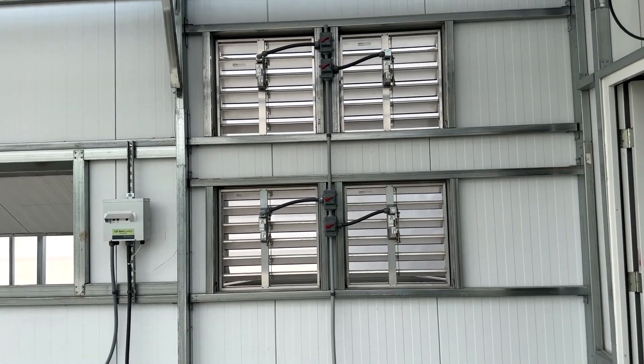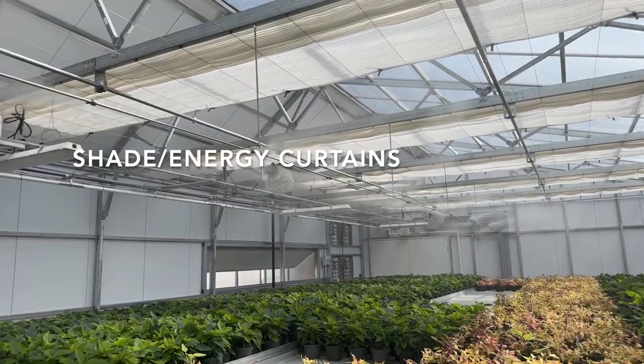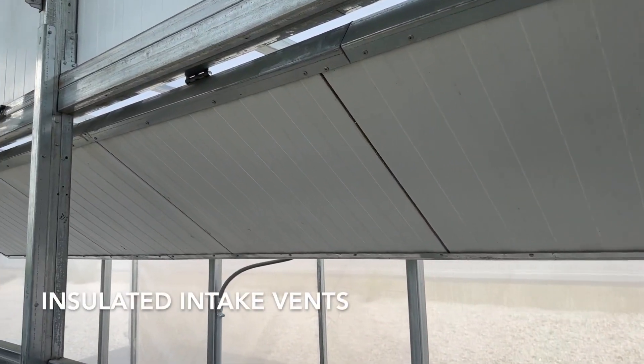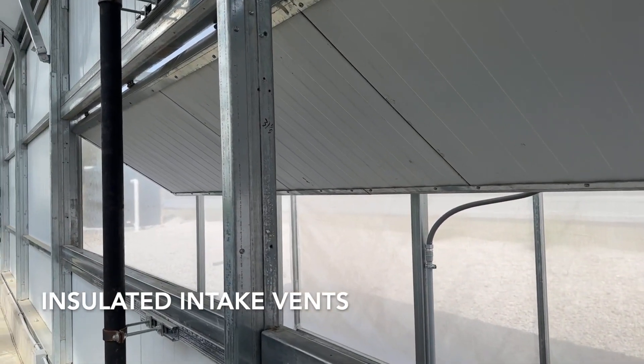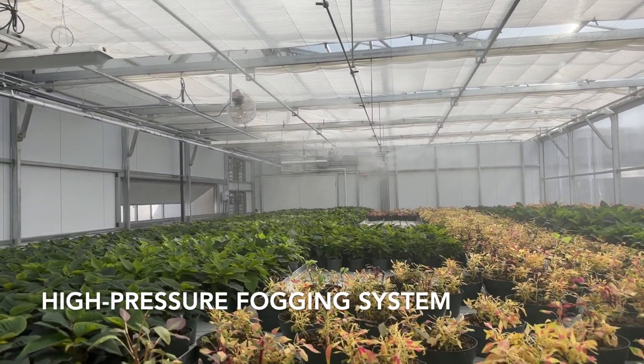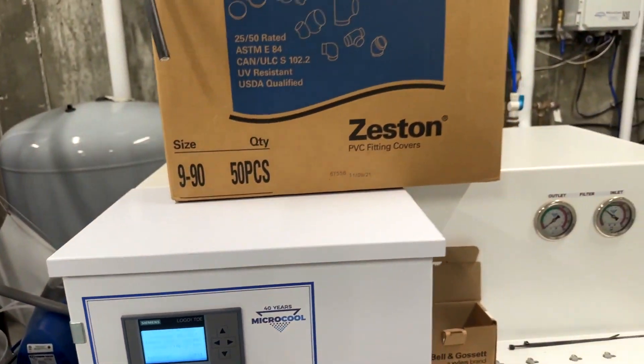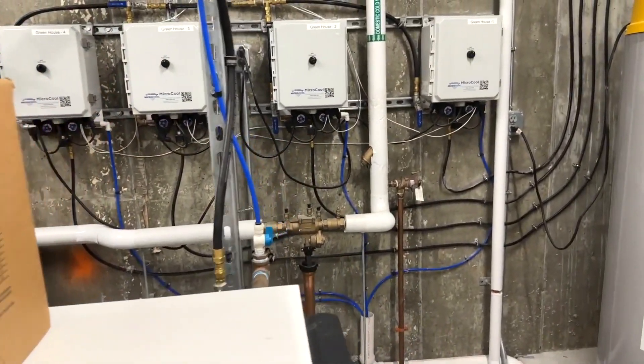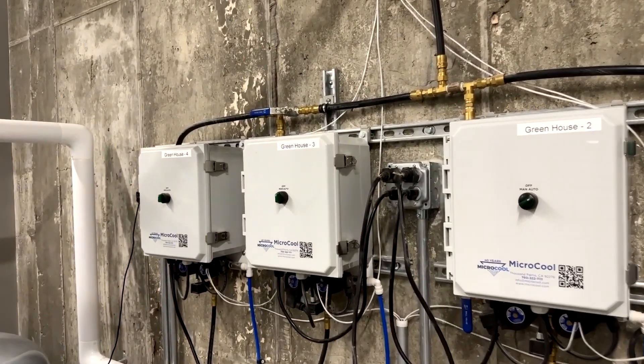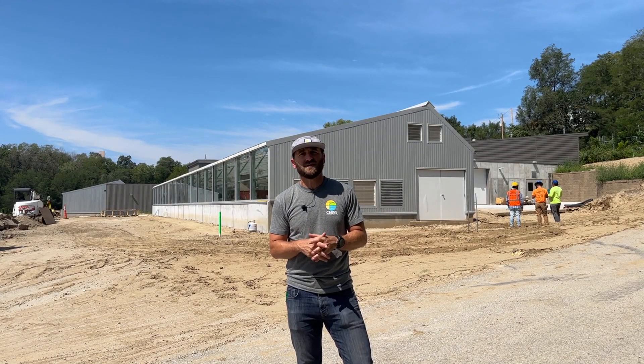It's beautiful and highly functional. The growers are excited, we're excited, and we could focus on just the greenhouses and the systems. These are vented greenhouses — all four of them. They all have shade curtains, energy curtains, exhaust fans, insulated intake louvers, and a high-pressure fogging system throughout. In a facility like this with four greenhouses, we can have one main pump and four zones, so one pump drives the fogging system through the whole facility, yet each greenhouse can call for fog when it needs it.